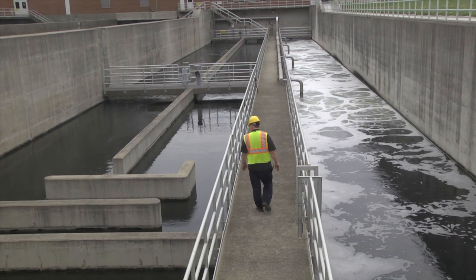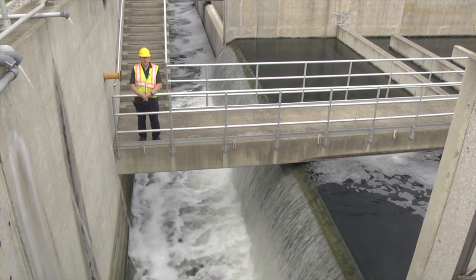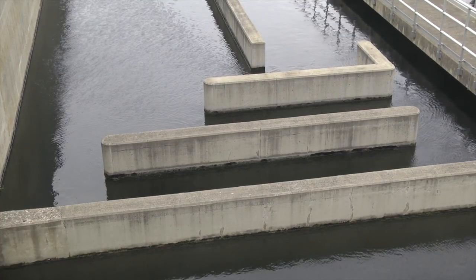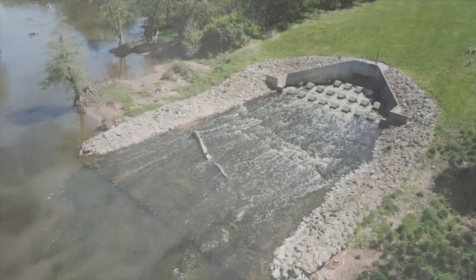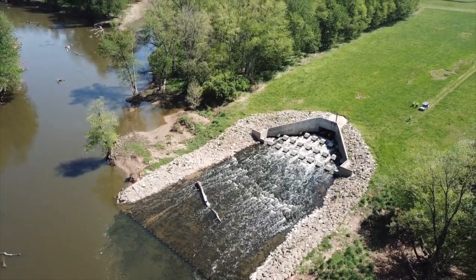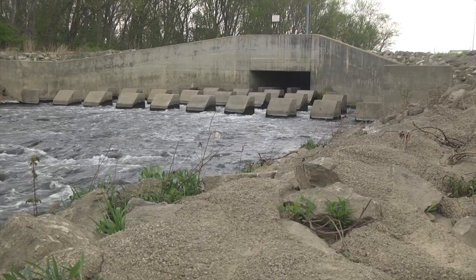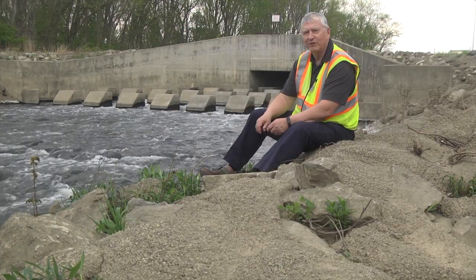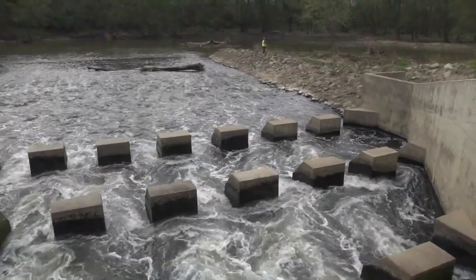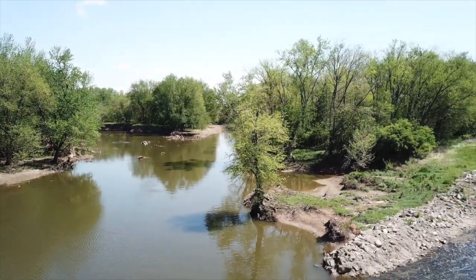Near the end of the process is the disinfection tank and post-aeration tank. Since the plant discharges into the river at such a large volume, it must maintain a certain oxygen level to avoid harming the stream, and must kill pathogenic bacteria before discharge. A couple hundred years ago, people lived in single-family homes with outhouses, and the stream could purify that small discharge on its own. But in a city of 1.2 million like Columbus, the concentrated stream totally overwhelms the river, requiring large community wastewater treatment systems to treat the water and return it for reuse.